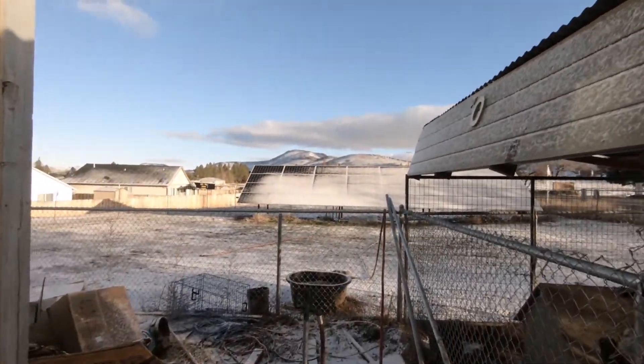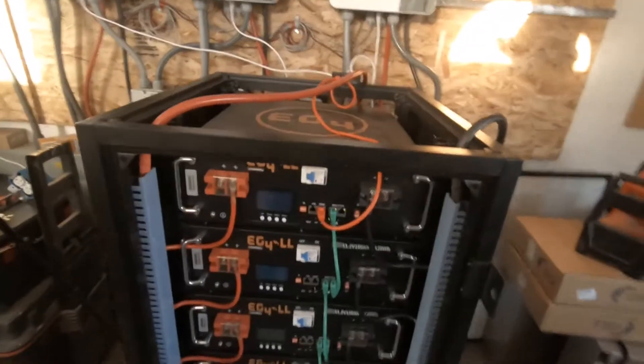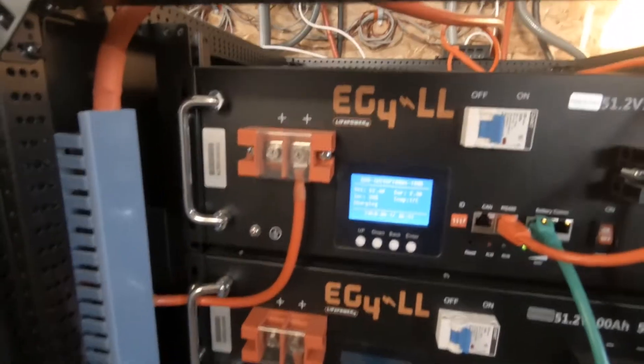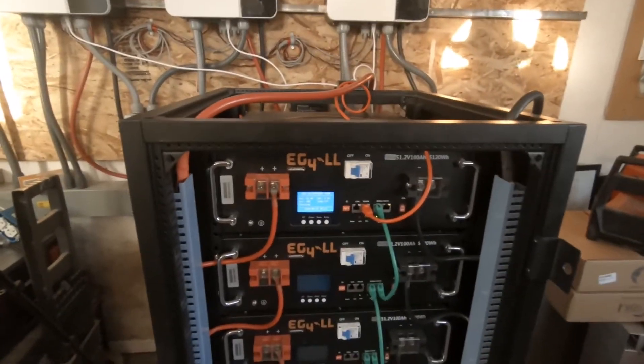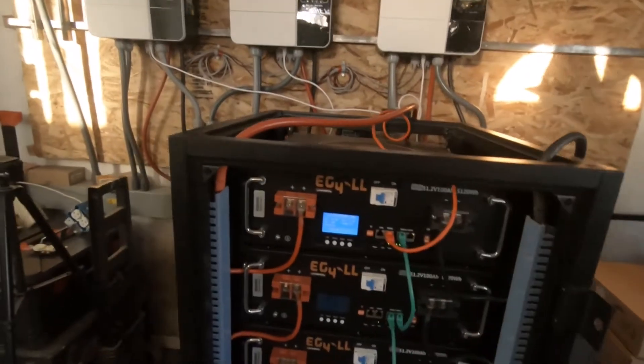I came out here and checked earlier - we had a dusting of snow last night, not much, but we had wind yesterday. This building I took down, there's some plywood I was trying to level out underneath. This is my power shed and this is heated. I've been staying about sixty percent state of charge on my batteries. Today we're down to thirty-eight percent state of charge - I went from 55 to 60 down to 38. We had winds yesterday, snow last night, and I was only at ninety-five percent state of charge at three p.m. yesterday.